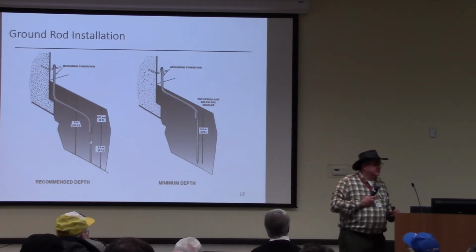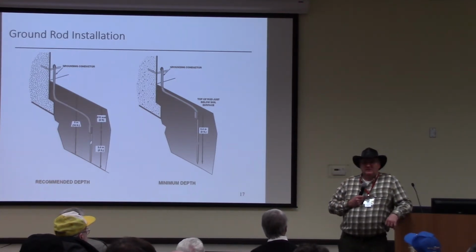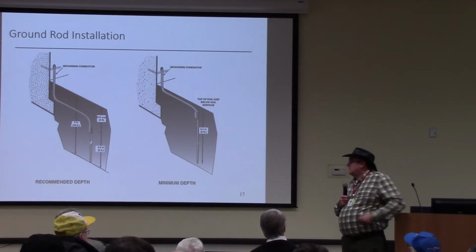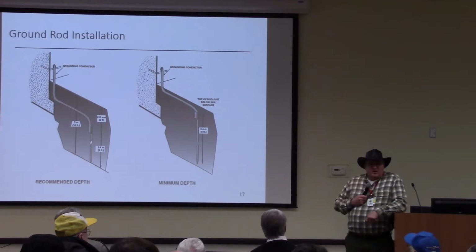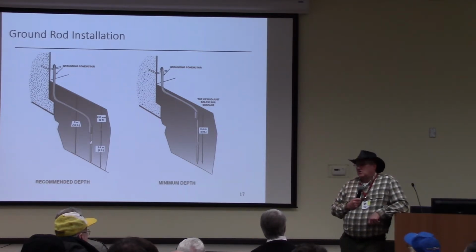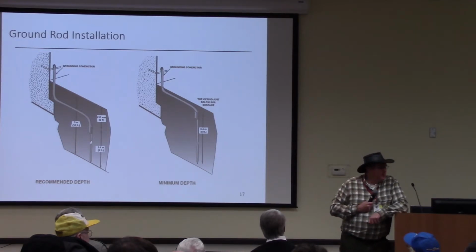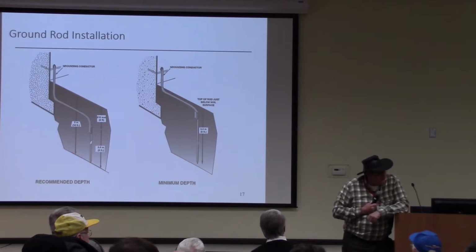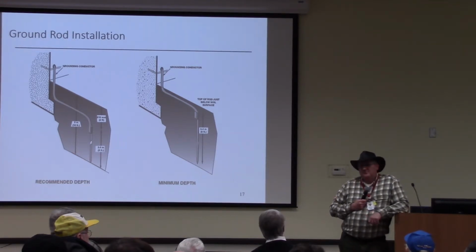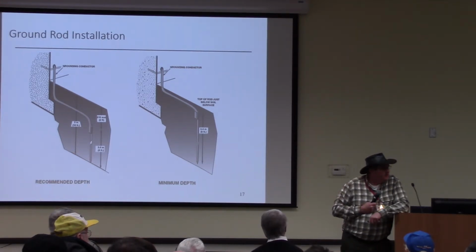They don't do that here. They leave the top end open and make the bond outside, up in this area. That allows the environment to get to it, that allows it to grow, that allows it to degrade. And you can't inspect it when it's under the ground. So it's kind of a trade-off as to how they want to maintain the standards, inspect it, and guarantee it versus what works.